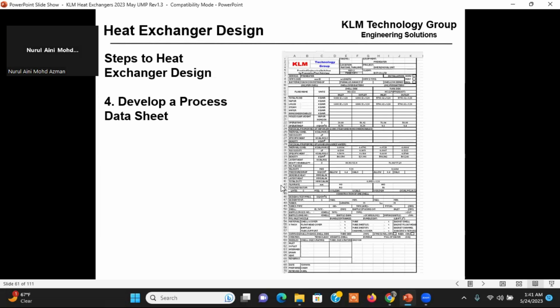Now, what the Coleman's handbook helps you do is to build this process data sheet from the process engineering point of view. So for a pump, it teaches you how to fill out the top half of this for a pump. For a heat exchanger, it teaches you how to fill out the top half of this for a heat exchanger. For a distillation column, it teaches you how to do this. So that's the purpose of the Coleman's handbook, to fill out the top half of this data sheet. Okay? And that's going to be one of your deliverables as a process engineer. Develop this data sheet. The process engineer's got to fill out the top half. The mechanical engineer's got to fill out the bottom half.